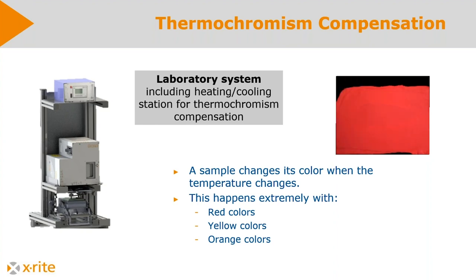So what do we do? We have the hot coil and we measure the hot coil, but what we want to know is how the coil looks like when we have room temperature. For this, we make a so-called thermochromism control. That means we measure the standard in the laboratory at different temperatures. And for this, we have this laboratory unit here on this table with a heating plate on the bottom. So we see how the color changes at different temperatures. And then I told you this ERX145 has also a pyrometer included. We measure the temperature on the line and recalculate how the color looks like at room temperature.